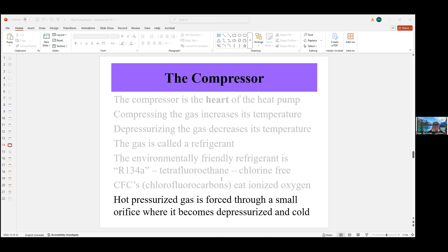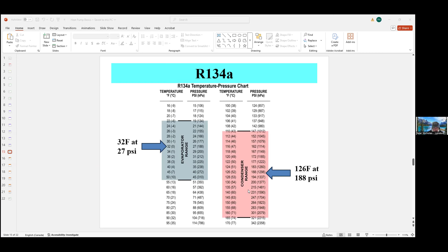The chart for temperature versus pressure for R134A, for example, at 27 pounds per square inch pressure, it would be at 32 degrees Fahrenheit. And if it gets pressurized, say up to 188 pounds per square inch, then it would be at 126 degrees Fahrenheit. And so that's how we get cold going through a heat exchanger and warm going through a heat exchanger.